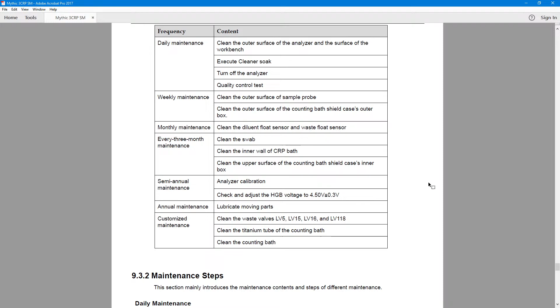Monthly, clean the diluent float sensor and waste float sensor. For the diluent, I believe it's not that important, but for the waste, since this part of the circuit is dealing with the waste, it's good to take a look at it to see if everything is fine and just wash it with some deionized water just to make sure that it will work fine.